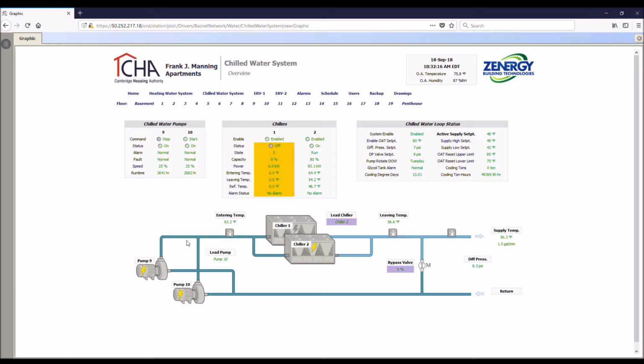It's when it gets hotter, obviously, that we need cooling. So when the outside air is above 60 degrees, we enable the system, and when we're below 60 degrees, we disable. The supply temperature is shown here. Actually, it's pretty high right now, and that's just an alarm. We have the actual alarm disabled right now, but that's just because I think we have all this heat transfer through the balancing, so all the heat from the boilers is kind of transferring to the cooling.